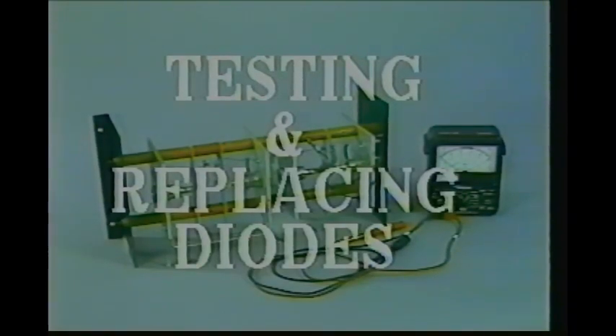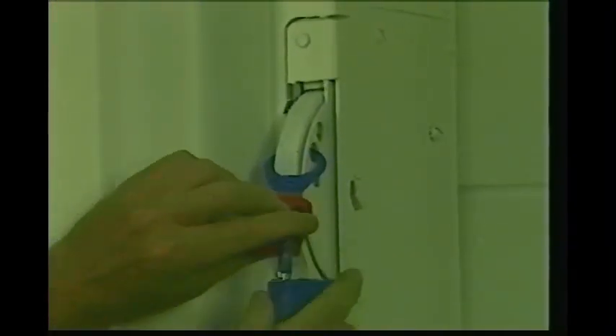Field testing and replacing diodes is a common test procedure performed when servicing welding power sources. Before you start, shut off all power and remove line fuses or lock or red tag switches to prevent the power from being accidentally turned on.